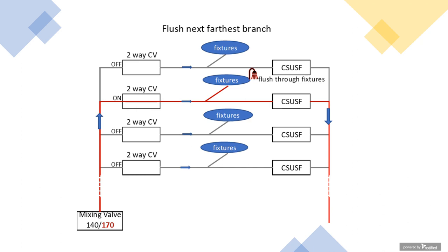So with practice, you could see that as soon as there's an instance of an issue, you could basically go in and within an hour have that branch thermally disinfected, which is a huge advantage over the traditional way people are trying to implement this. So it's very powerful.